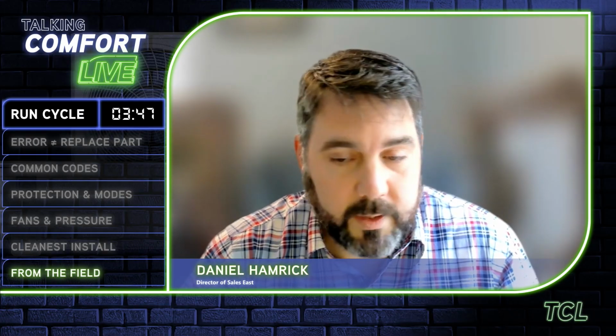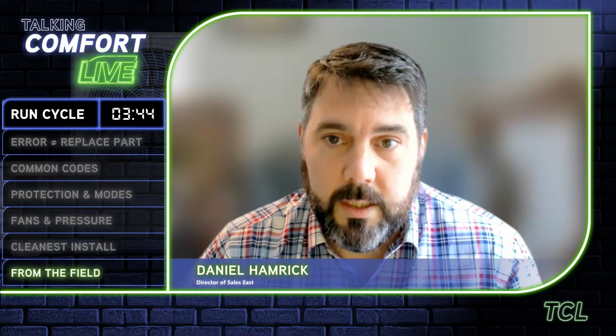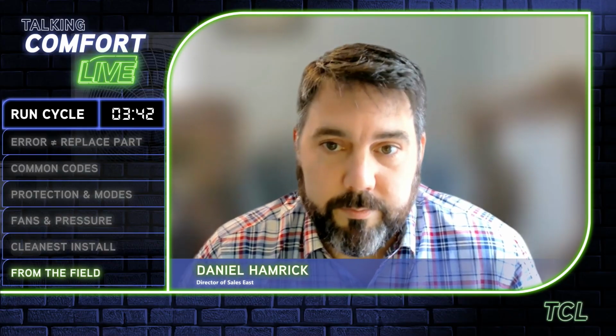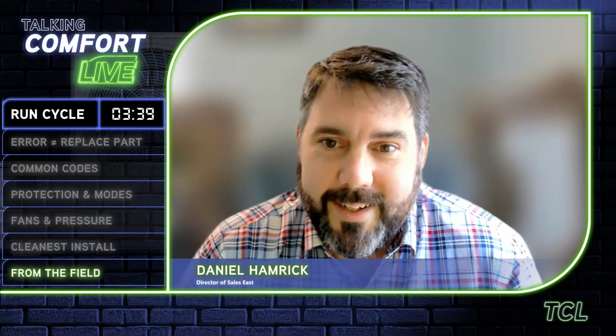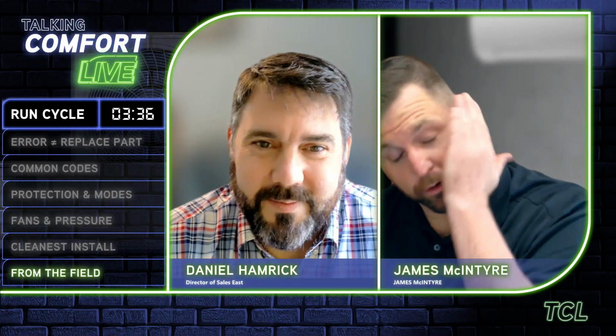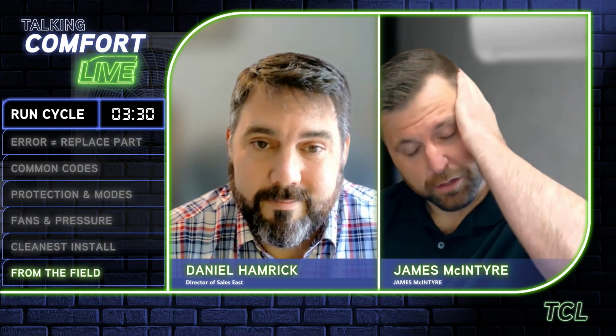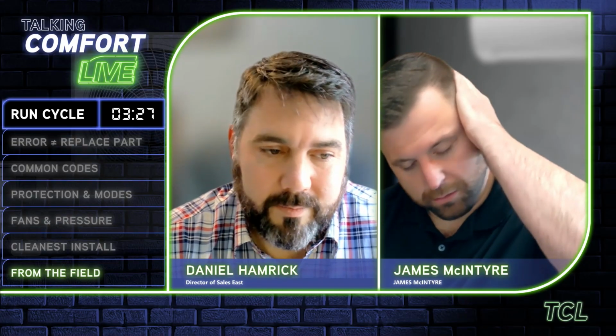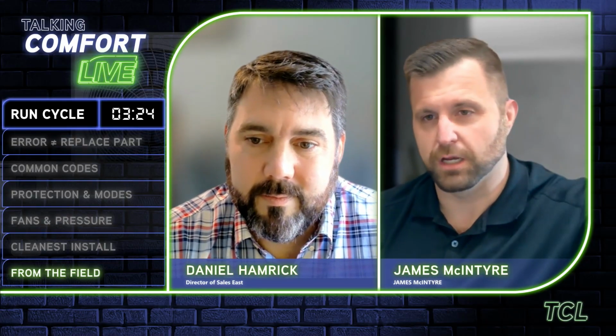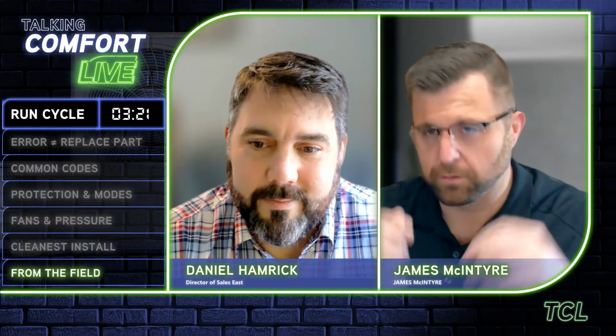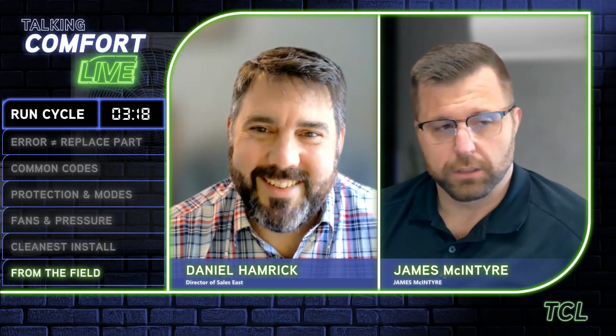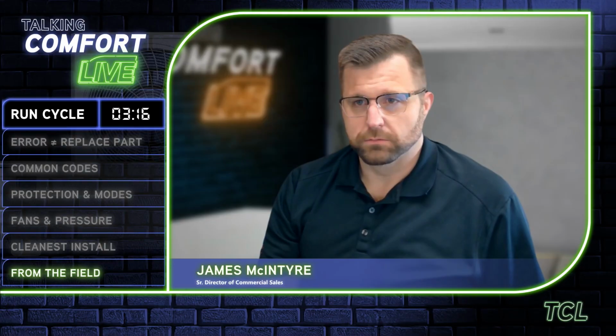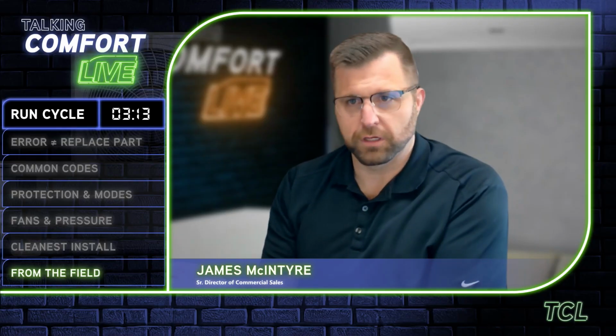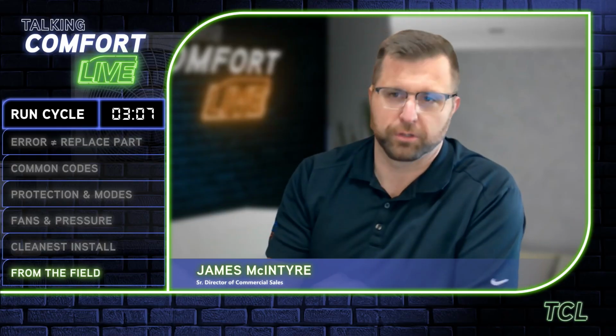I know everyone that's watching today does a heat load every single time. But I tell you what, even if you are doing a heat load calculation, it's as accurate as the information that you input. Like I can think of one example right now where, let's say it's a room that's got a bunch of windows and you size the equipment based on like 2 windows. Well, I understand the heat loss or heat load calculation says that this is what capacity that you need, but the information that you put in, it's garbage in, garbage out.